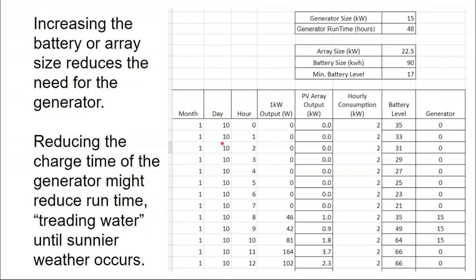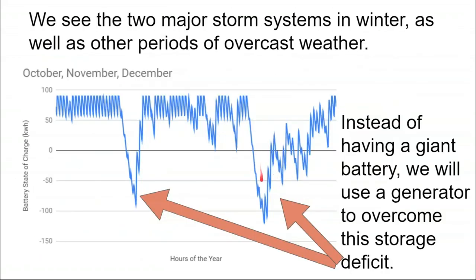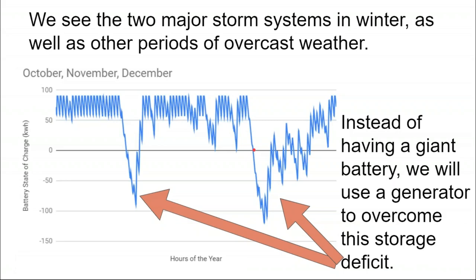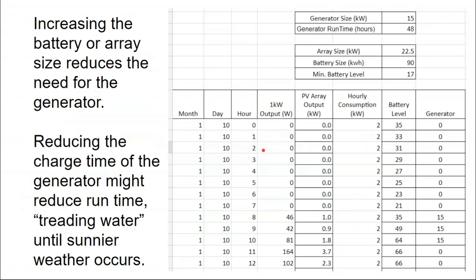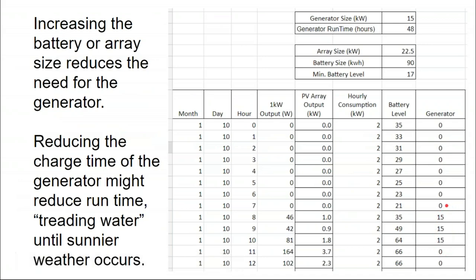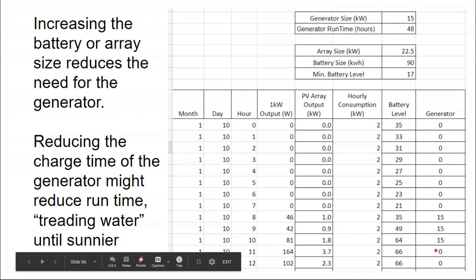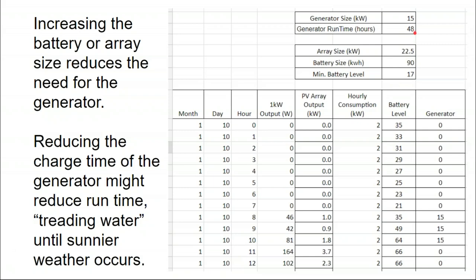What I basically do is look for this critical patch, this one patch, and say, okay, what do I need to do in terms of generator runtime to get back up to the top? So in my spreadsheet model, I'll calculate how many hours of the year my generator ran at full capacity and judge that against the cost of gas to run the generator versus the upfront cost of increasing the battery bank size. You can toggle the battery bank size and reduce the generator runtime as an economic optimization.